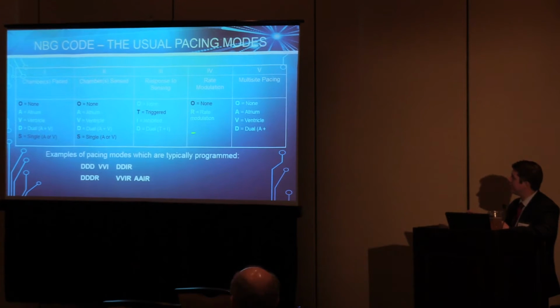The other is the response to sensing. So what happens when it senses? You can have triggered activity, which is an interesting programming. Sometimes we'll use that, but mainly what you'll see is either I or D following in the third position. I meaning that it inhibits. So the main job of a pacemaker is to sense the chamber that it's pacing, and pace the chamber that it's pacing. So inhibit mode would allow it to sense and not pace should it sense a native beat. Dual would allow it to do both. And then rate modulation is also present. There's some other multi-site pacing which typically aren't mentioned to you guys in our programming, but it is included here for completeness.